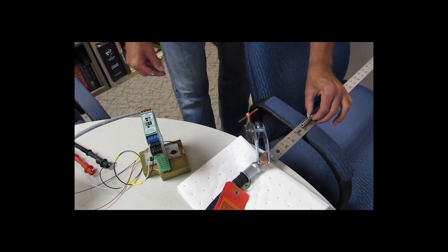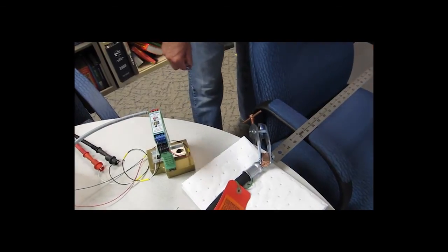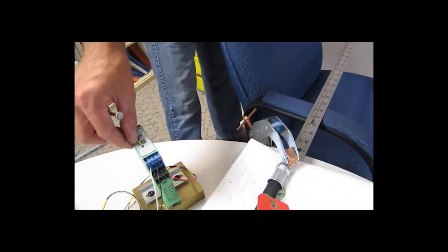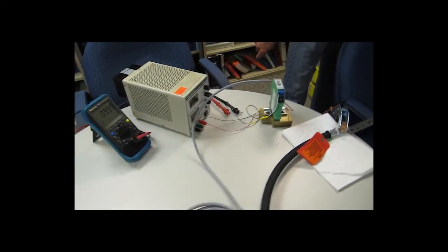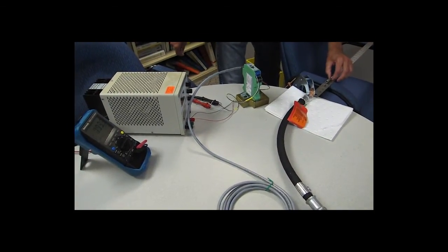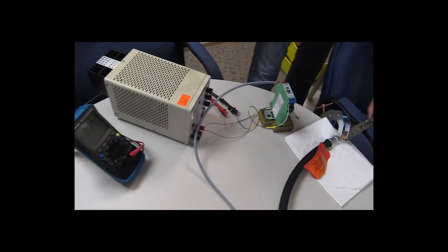Okay. And now we'll move the cable to, let's say, 36 inches. And press the full scale. And if we look at the voltmeter, we now have zero to 10 volts between five and 36 inches.